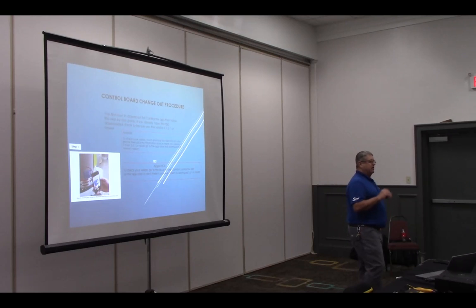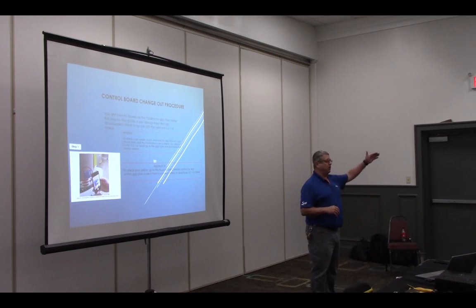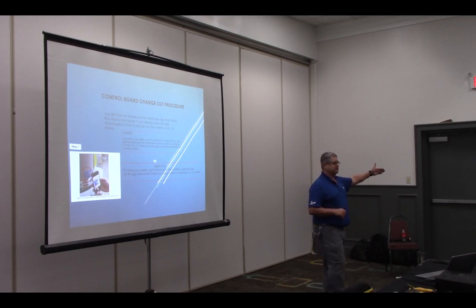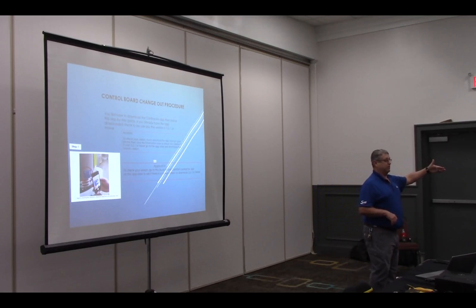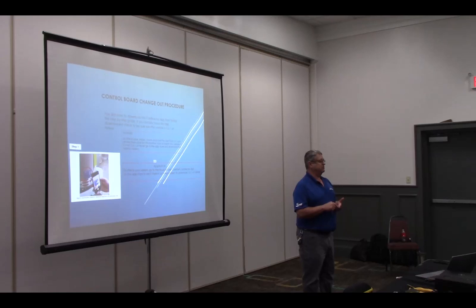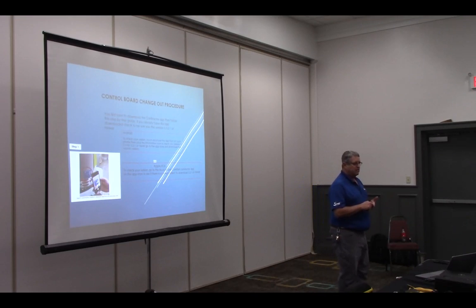We'll tell you now, if you install this 15, 16, or 18 SEER equipment, it could have been sitting on the shelf a whole year by now, right? How many updates to the software in that board have come out since then? What do y'all think? Probably a bunch, right? Even if it's been on the shelf 6 months or 3 months, how many updates have come out? If you put any of this equipment in, I would recommend updating the boards prior to installing them. With the 15 and 16 SEER, if you install a 3-ton or a 5-ton, you have to update the outdoor board. Because I can tell you there's been updates to those two pieces of equipment, the 3-ton and the 5-ton, 15 and 16 SEER straight cool or heat pump, okay?